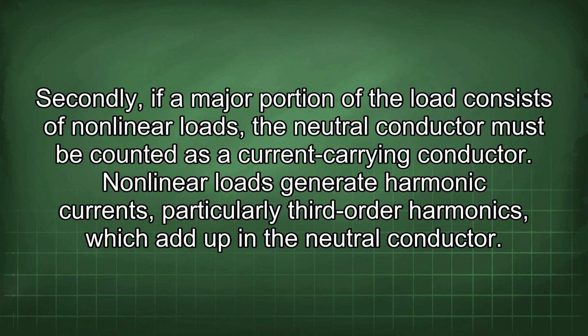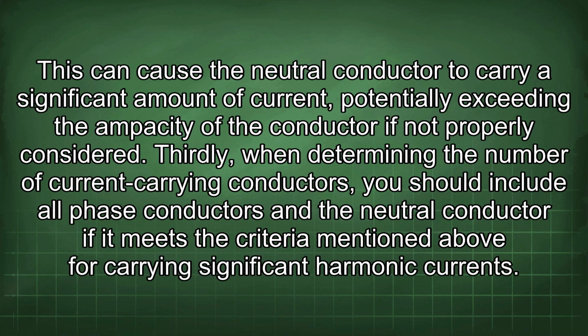current carrying conductor. Nonlinear loads generate harmonic currents, particularly third-order harmonics, which add up in the neutral conductor. This can cause the neutral conductor to carry a significant amount of current, potentially exceeding the ampacity of the conductor if not properly considered. Thirdly, when determining the number of current carrying conductors, you should include all phase conductors and the neutral conductor if it meets the criteria mentioned above for carrying significant harmonic currents.